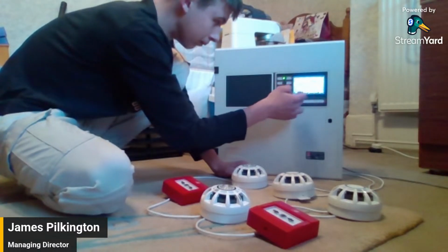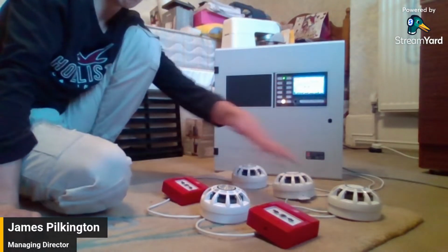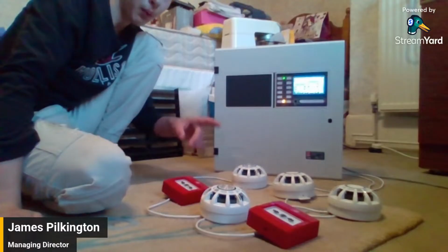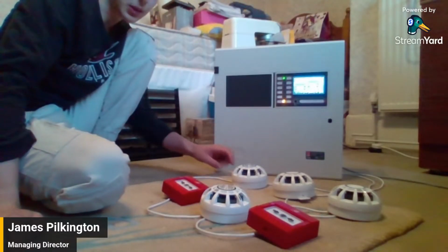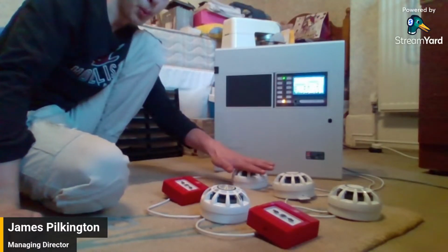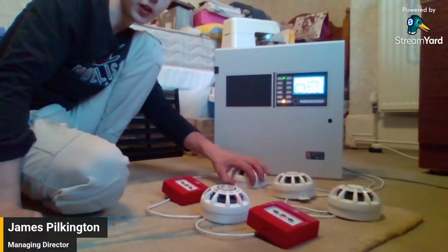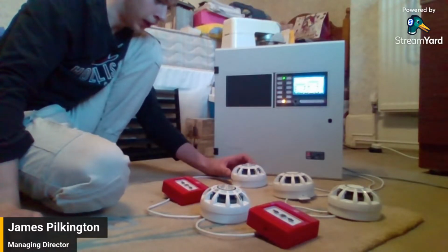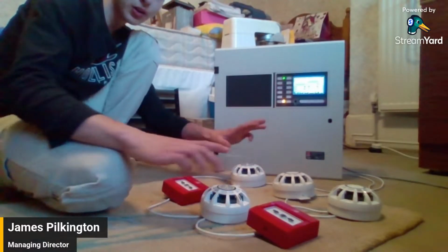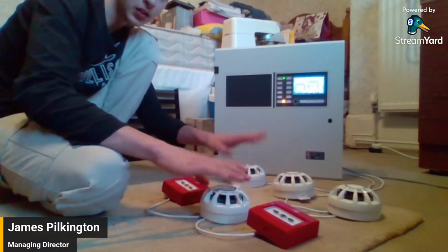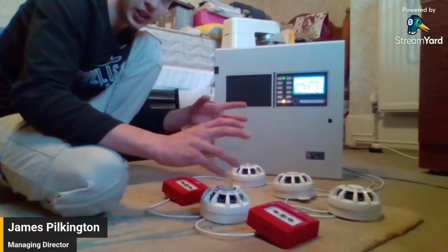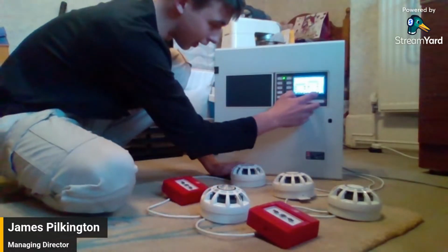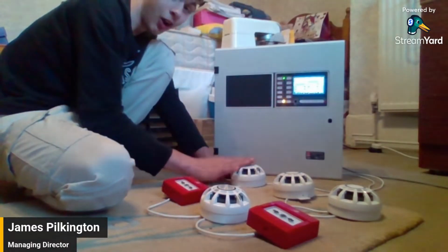So all output devices would be your normal sounders. I will come into this in the cause and effects programming because the output groups can be quite crucial when you are programming cause and effects in. So later on, I'm going to show how to make the VADs continue to flash while the system is silent. And that is done by putting the VADs in their own output group.